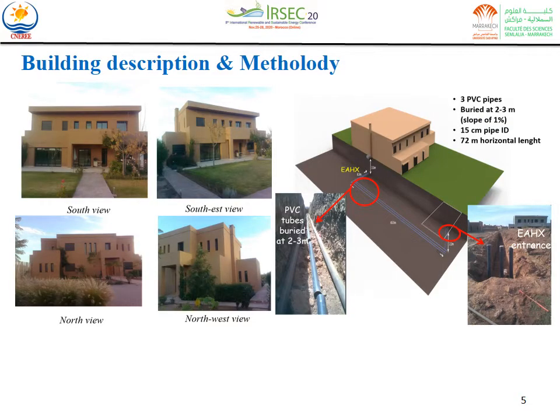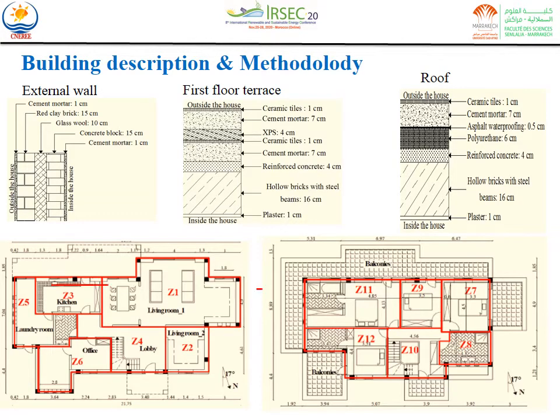The building considered is a villa type located in the suburb of Marrakech in Morocco. This building contains many passive and semi-passive systems, and one of them is the earth to air heat exchanger, which consists of 3 parallel PVC pipes of 72 meter length each and 15 centimeter diameter, buried at 2 to 3 meter depth. And each pipe is equipped with a fan which blows air into the building. The external walls, as well as the first floor terrace and the roof, are well insulated, but the case of the building without the insulation materials is also considered in the study.